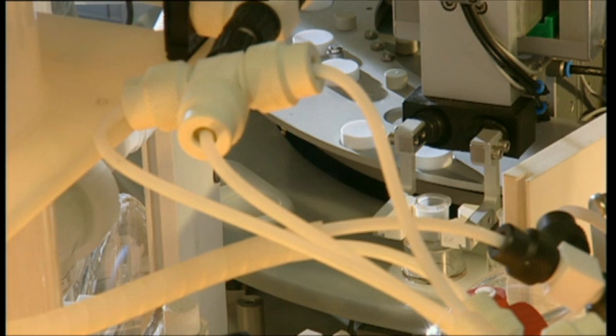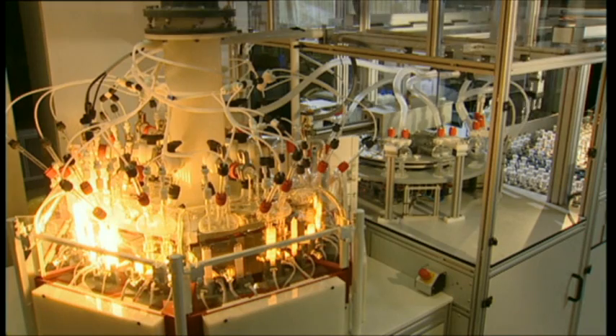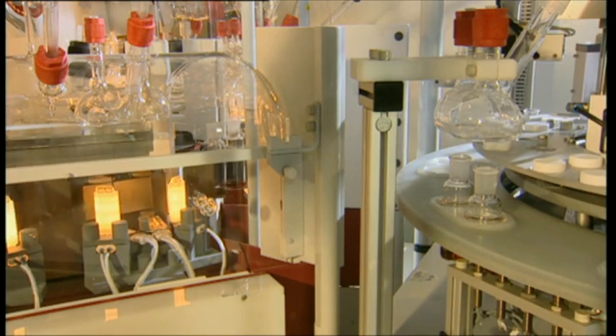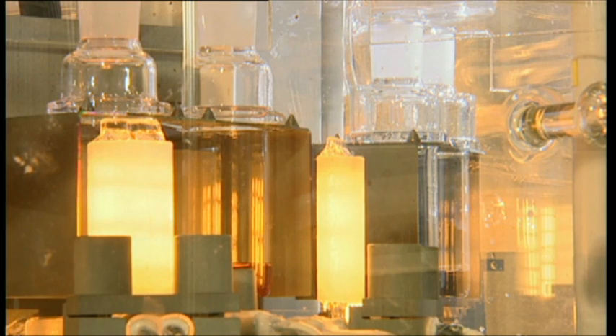Here, a second robot arm transfers the bottles to the digestion carousel. A hatch opens and the bottles rotate into the digestion carousel, where the samples are heated slowly. The heat sources are IR heaters, which can heat the sample bottles very efficiently.